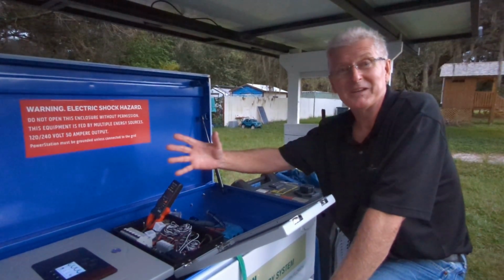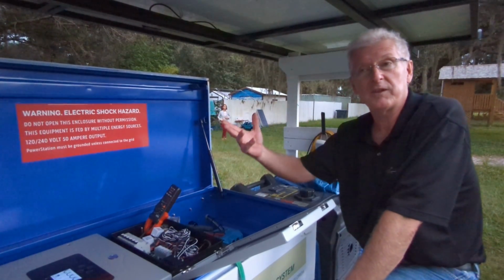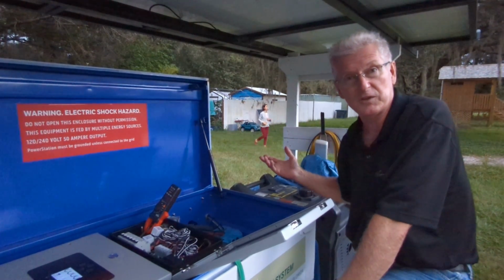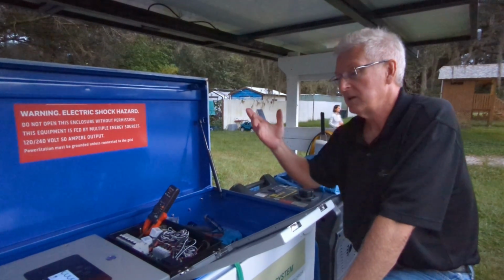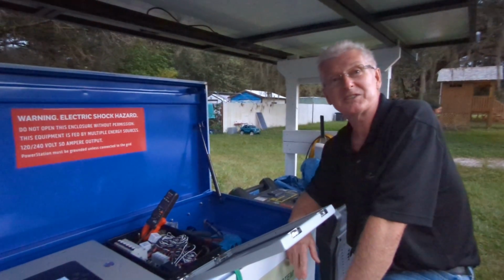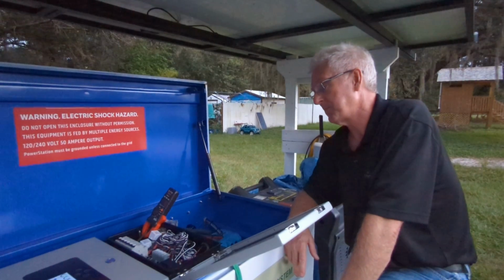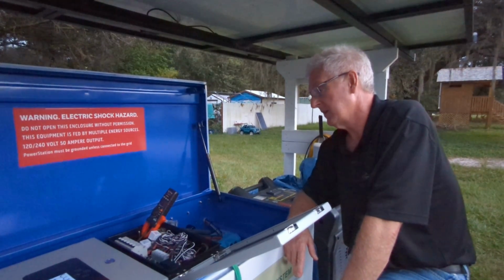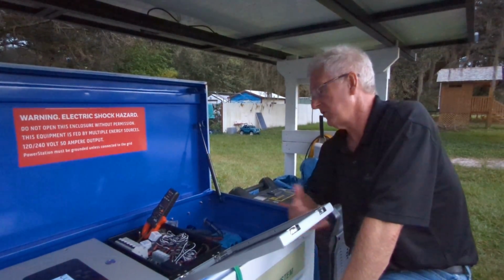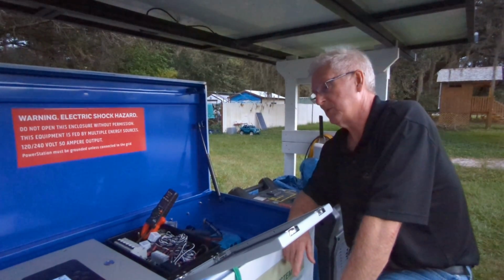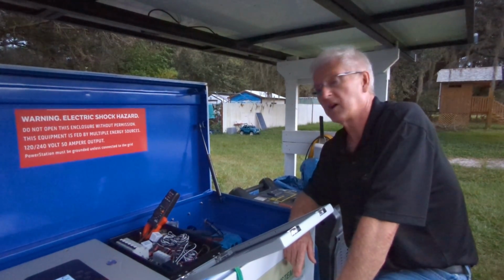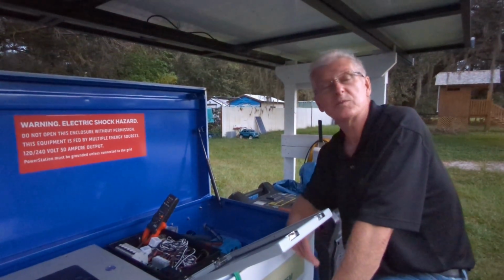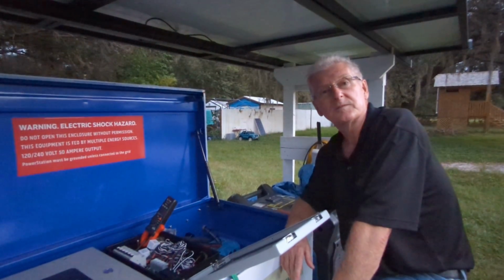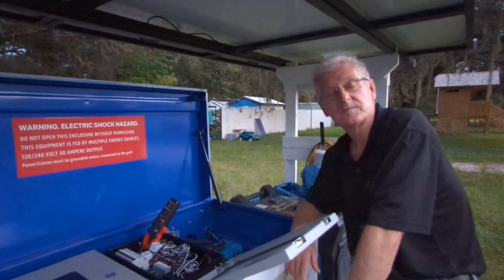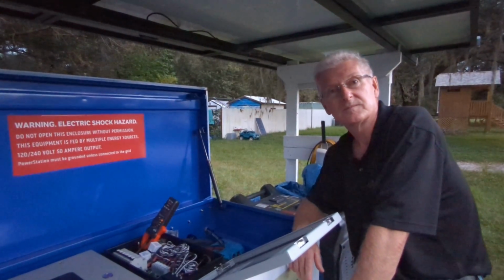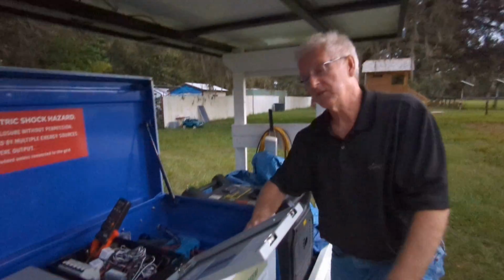We just don't know. So what you want to do is before the next scheduled start for the generator for 20 minutes, just come on out here and wait. See if it starts. That's right. Just make sure the key's on. What's left? Really, the only thing that you could do to improve the system would be to get soft starts on your ACs, at least one. Yeah. And the other thing that you mentioned, you said you wanted to even put it in this box. The auto transformer.